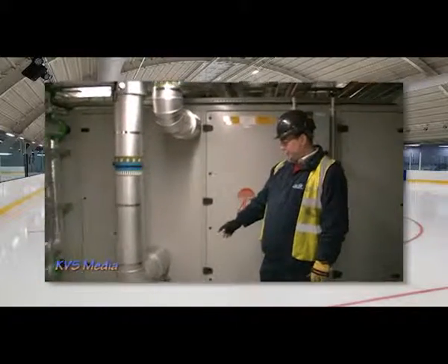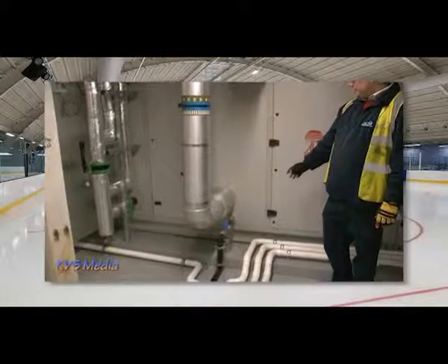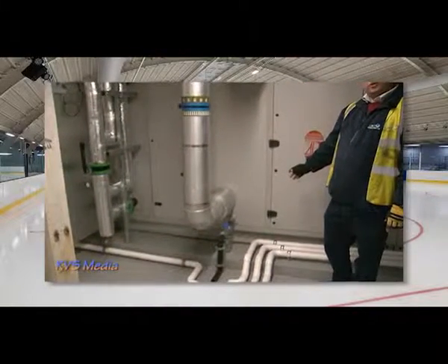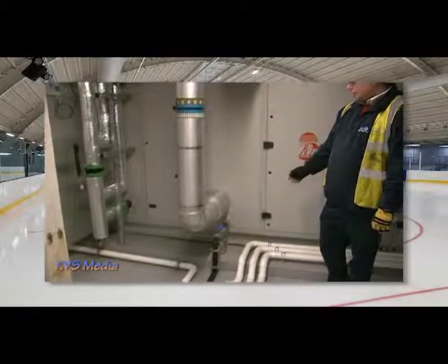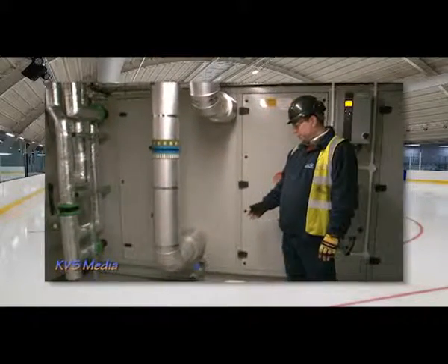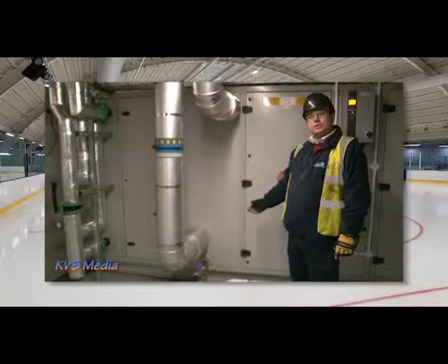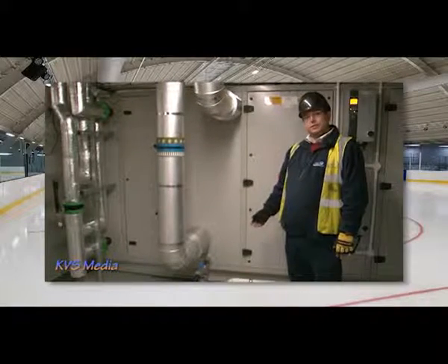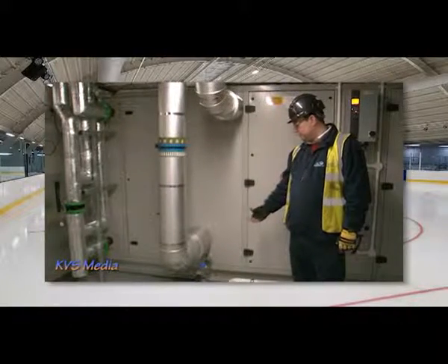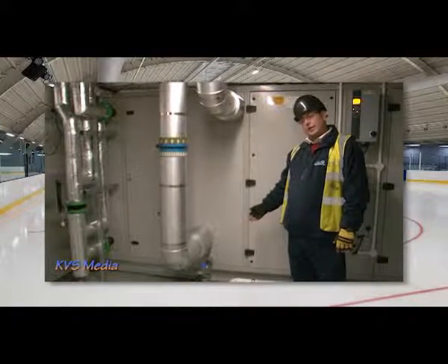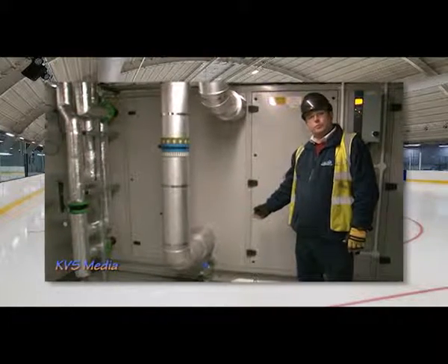Down below we have a glass U-trap, which is a good indication for moisture being removed out of the system. This, in certain conditions, will not run, but during the summer months it would constantly expect to see water, so it's a good maintenance to get into to make sure that's kept clean, just with a general bottle brush.